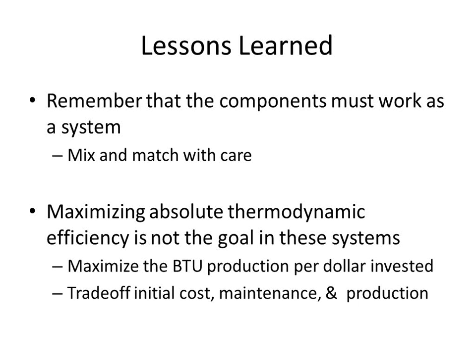Now, that does tend to correlate with system efficiency, because if I need 5 times more collectors, that's generally going to be more expensive. But comparing a system with a collector that's 92% efficient versus one that's 87% efficient may not make any difference if that 87% collector is going to last twice as long, or costs 30% less, or allows the glycol to last 10 times as long. So that's not immediately obvious, but thermodynamic efficiency isn't the goal.